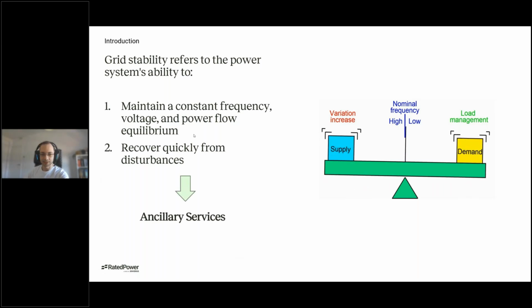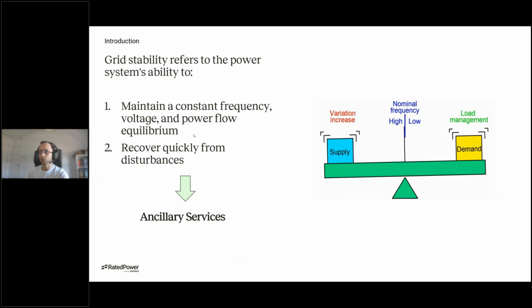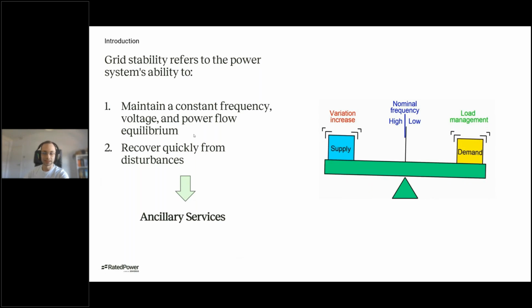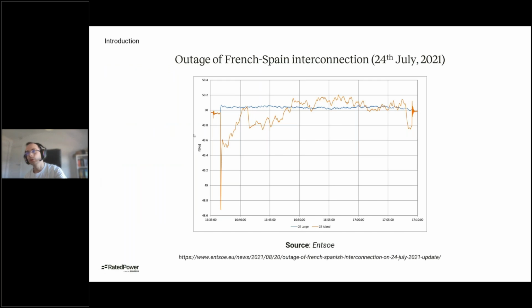Ancillary services are the tools that allow the power system to recover from these disturbances and to keep this equilibrium. And I want you to understand the importance of these services through an example. This is the chart of frequency during an outage in the French and Spanish interconnection on the 24th of July of 2021. This happened because of a fire. So you see, in July, a really hot summer. Because of a fire, France and Spain lost around 2.5 gigawatts of power because of an outage in a transmission line. This resulted in a big drop of frequency in the Spanish part and a slight increase in frequency in the French part.